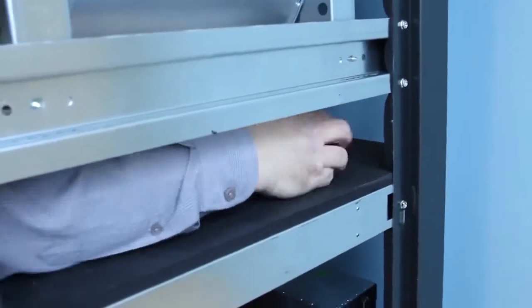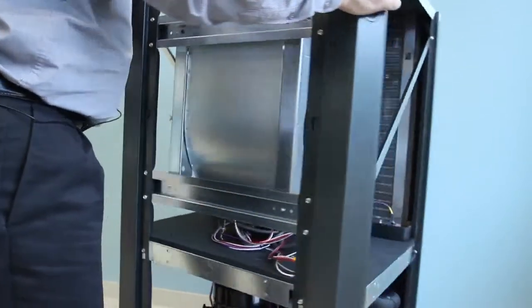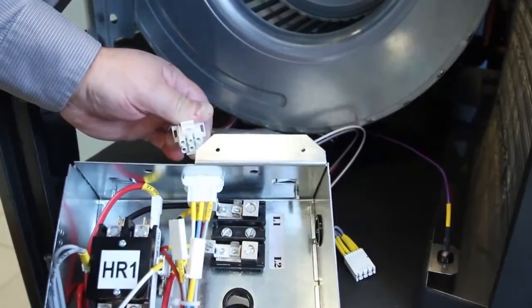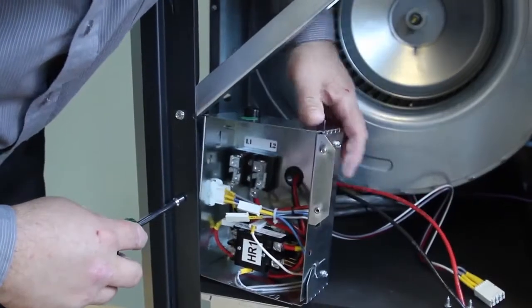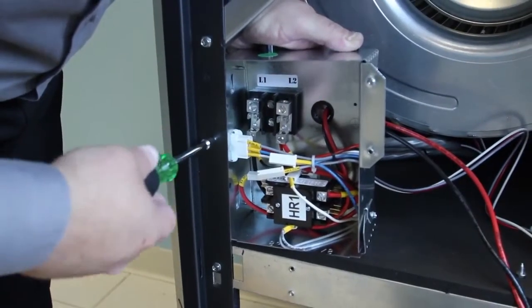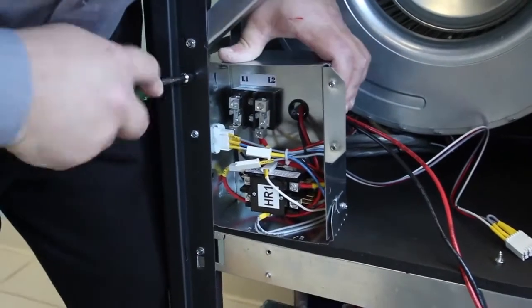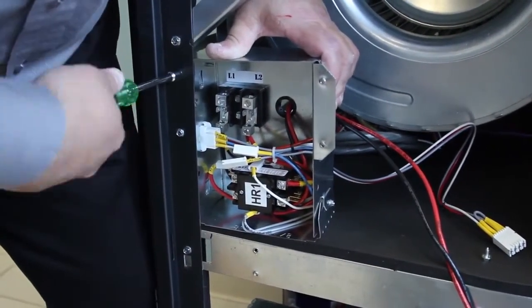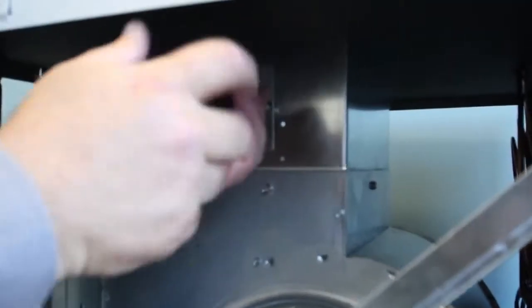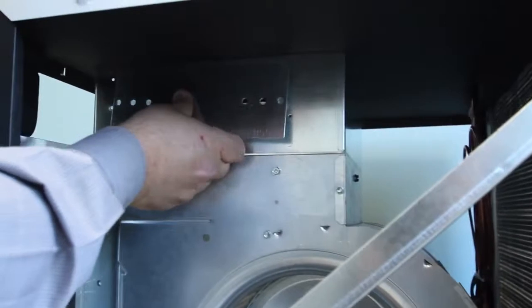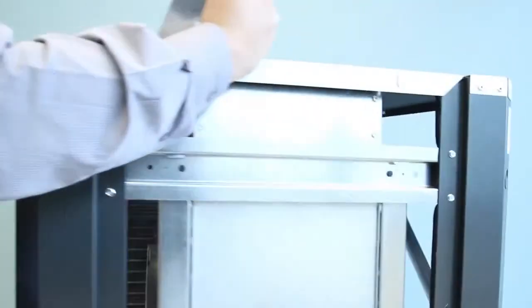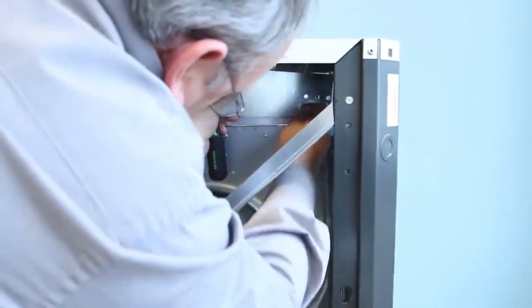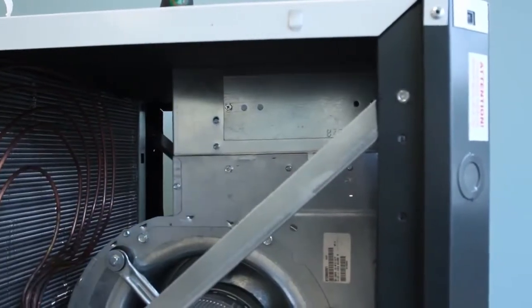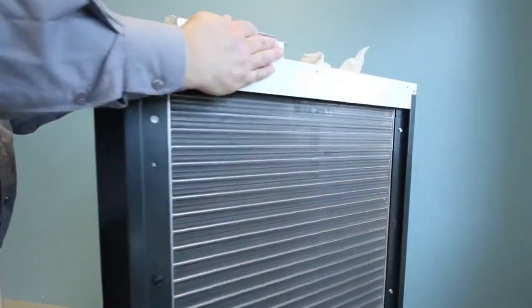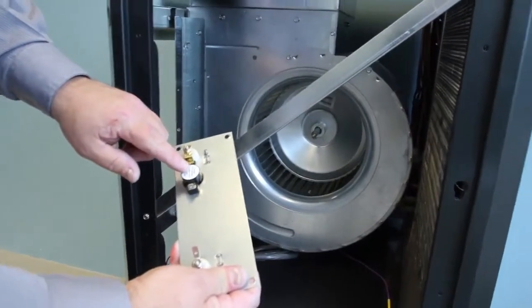Once the e-box and the elements are removed, you can rotate the unit 180 degrees so that the return air is on the right-hand side of the unit and reinstall the electric e-box in the new location illustrated in figure 77 on page 22. Remove and retain the blower collar covers shown in figure 78 on the front of the blower collar in the new position. Reinstall those covers in the openings on the opposite side or the original side of the blower collar. Once that is done, reinstall the electric heat elements in the new location, ensuring that the high temperature cutouts are located on the left side.